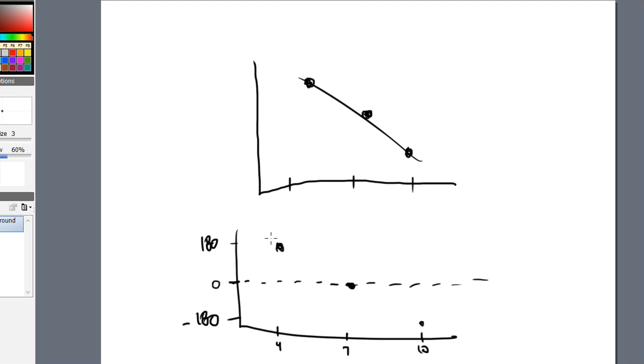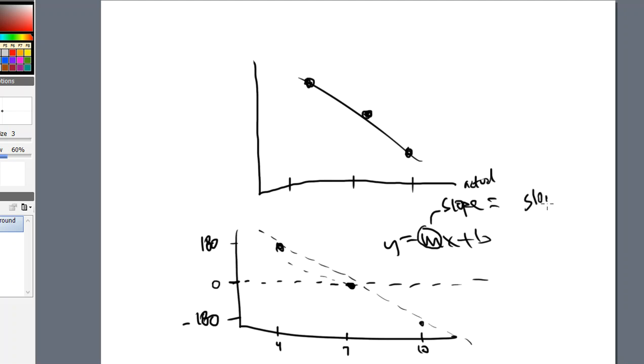And if I make a straight line, then I hope that these 3 dots make a straight line, and I will get y equals mx plus b. All right, what will happen is that the m value is the slope, and we know what that value should be. And that actual slope, because this is what I actually did, because I actually ran it and did an actual calibration curve, will be compared to the theoretical slope. And that theoretical slope and the actual slope will be calculated and will pop out a number that's called a slope percent. And a slope percent is kind of like the accuracy of the pH probe.